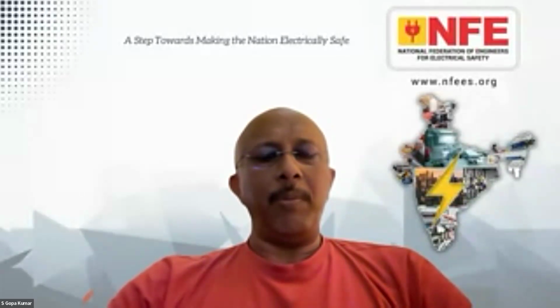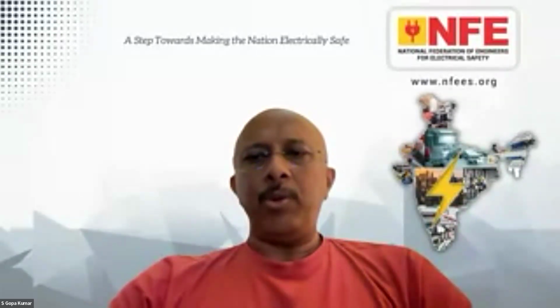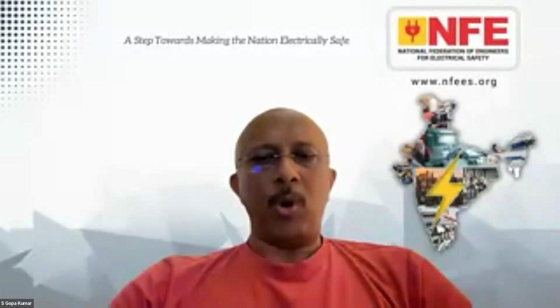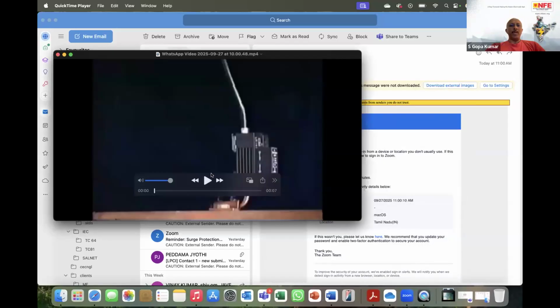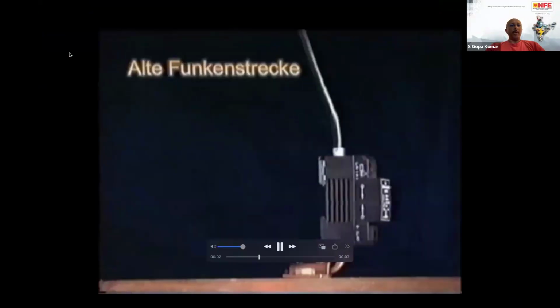And there was a MOV based SPD, which was Type 2. I would like to show you an interesting small video of how the Type 1 spark gap SPDs were working. You can see in this particular movie, this is a spark gap SPD. During the initial days, the spark gap SPDs were exhausting type. Exhausting type means the spark which was created inside the gap was blowing out. They were also called blowout type SPDs. So spark gap SPDs were highly dangerous during that time.